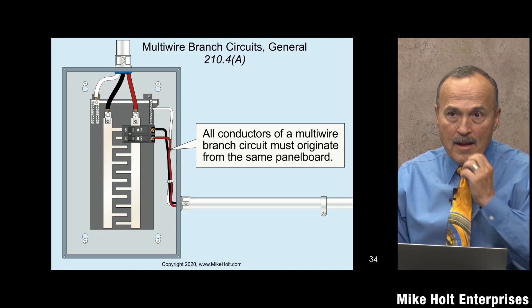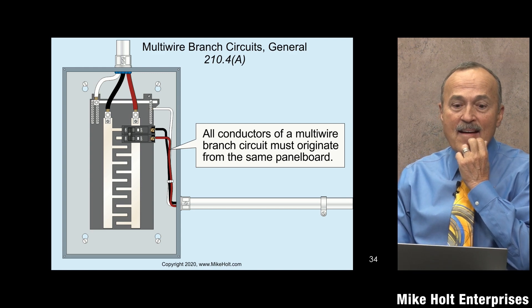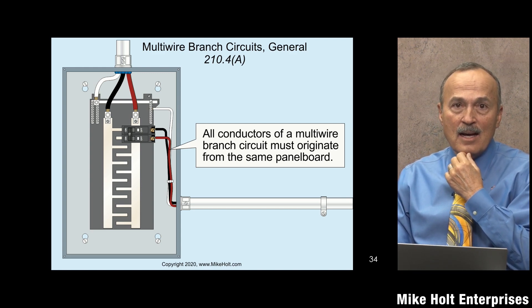This rule is very relevant. For new people, understand this is not a mechanical workaround — there are real reasons why circuits must come from the same panel. We saw this in a house in Florida with two panels: branch circuits came out of one panel and all the neutrals went back to the other. The lesson: do not get creative. Follow the code. It's a good way to get yourself into trouble and cause extra hazards.